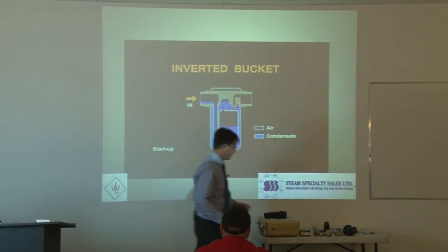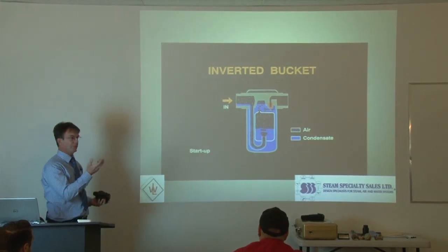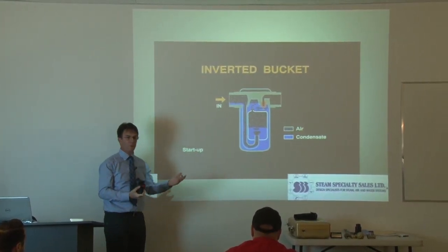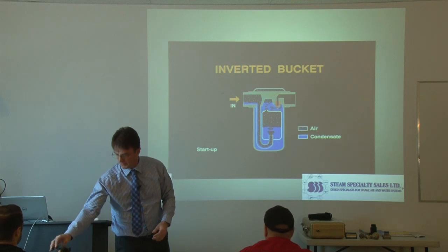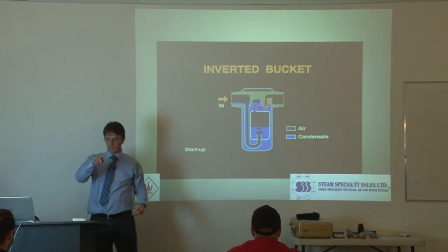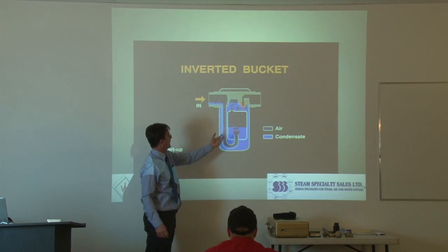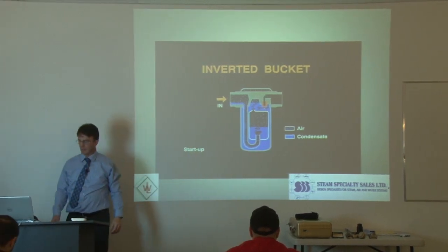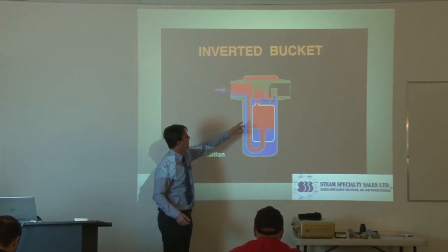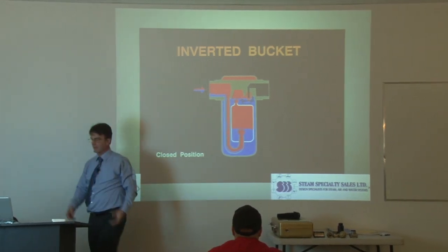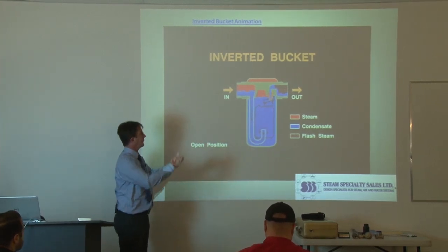Inverted bucket traps don't modulate like a float trap — they're more on-off, like a solenoid valve or ball valve that opens and closes. The orifice is the hole on top. When air and steam get inside, the bucket becomes buoyant and rises, which closes the trap. When steam starts to escape through the small hole at the top of the bucket and condenses, the weight of the bucket overcomes whatever steam is left inside and it drops down.